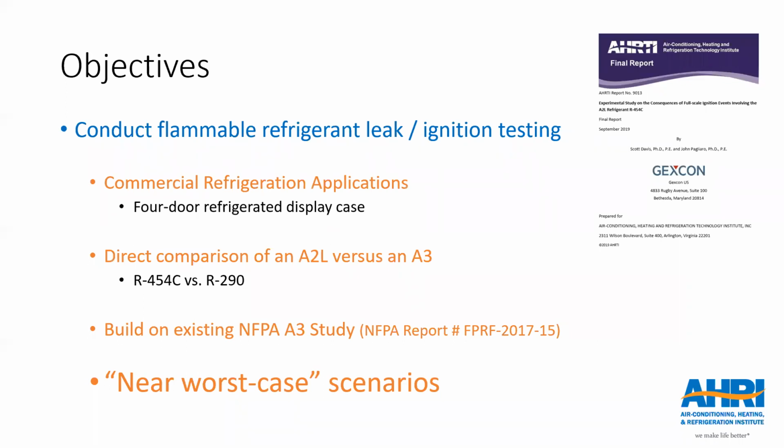Now, one of the main goals of this study was to do a direct apples-to-apples comparison, as much as possible, of the refrigerant leak and ignition testing behavior of an A2L versus an A3 refrigerant, using the same test setup and the same test methodology. Here we used R454C, an A2L blend, and R290, which is refrigerant grade propane.